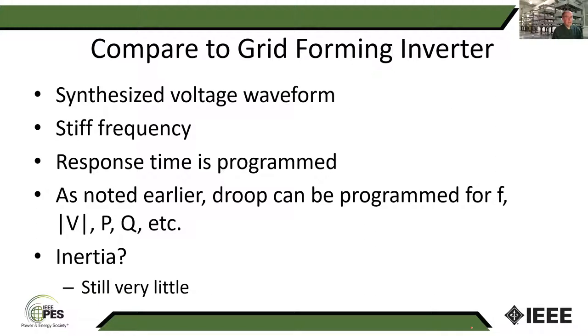Some thoughts would be, and this is something that they did some experiments with on a PV installation in California, as we go through the course of the day, usually the PV output on a nice sunny day without clouds follows this. What they did was, when they got to a certain point of day, instead of following this, they moved the reference down here, and the inverter was able to increase or decrease its output to meet ancillary needs for the power system. So basically provide frequency regulation. You could also try to do something like this to imitate inertia if you wanted to as well.